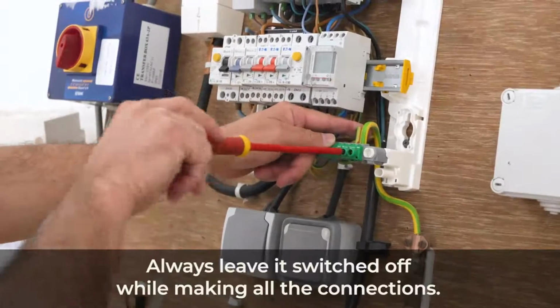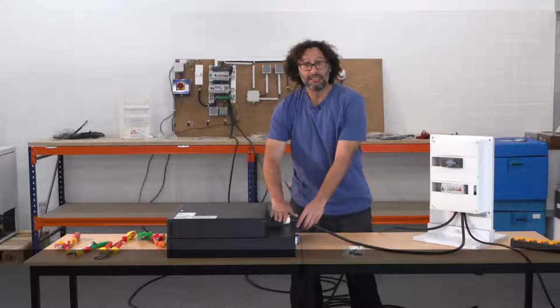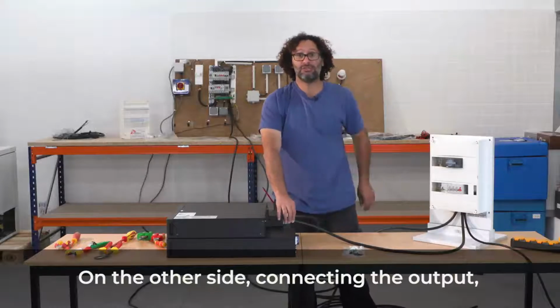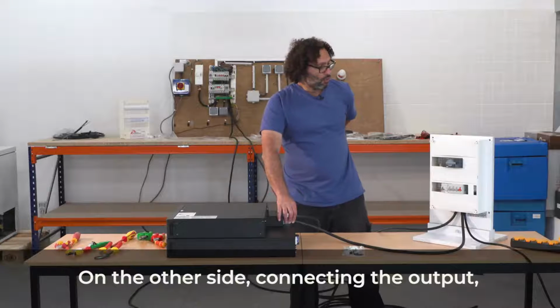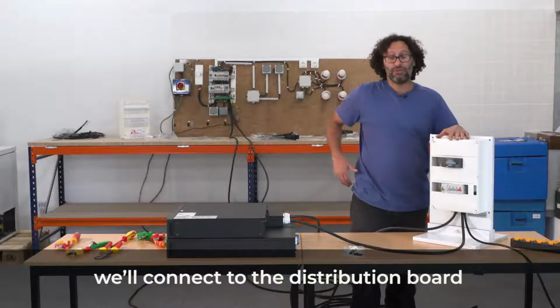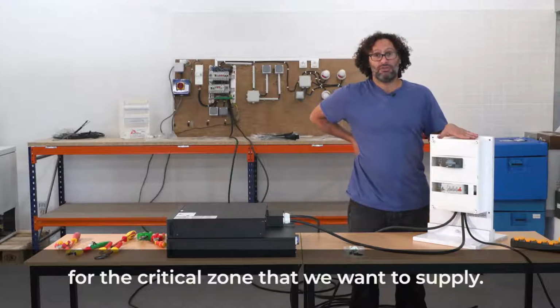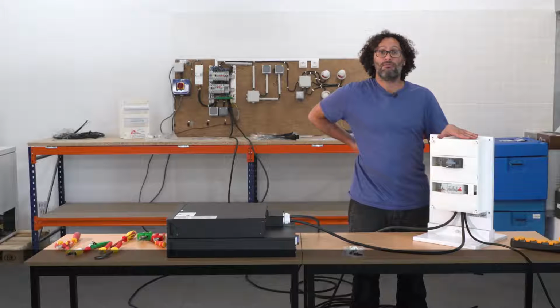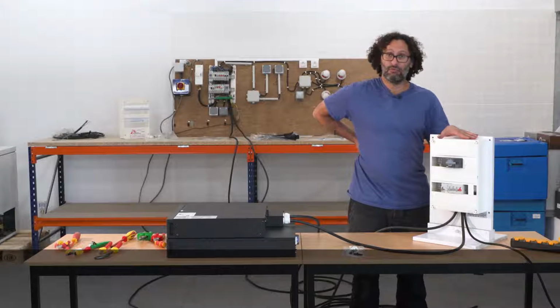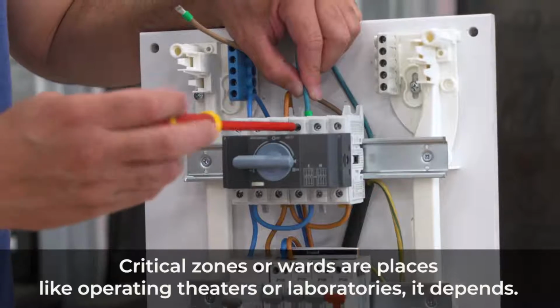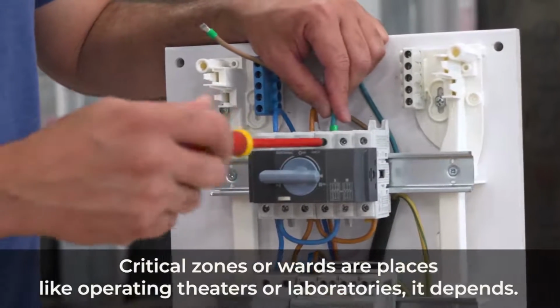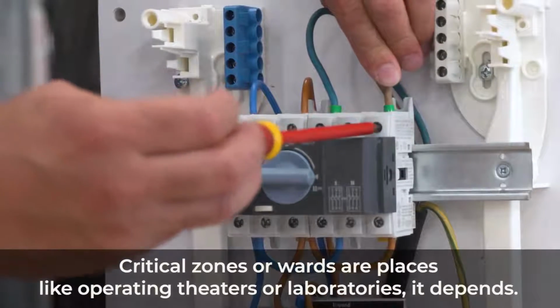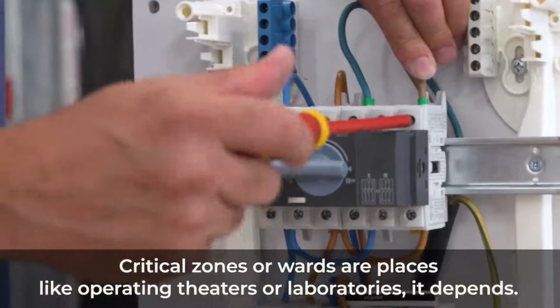Always leave it switched off while making all the connections. On the other side, connecting the output, we'll connect to the distribution board for the critical zone that we want to supply. Critical zones or wards are places like operating theaters or laboratories, it depends.